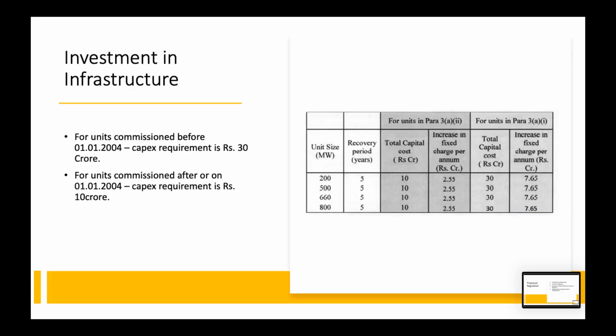The increase in investment in infrastructure is considered on the basis of unit commissioning date. For units which have been commissioned before 2004, an investment of rupees 30 crore has been considered for the unit in order to do the necessary modifications to run and stabilize at 40% load. For units which have been commissioned after 2004, an investment approval of rupees 10 crore has been considered.